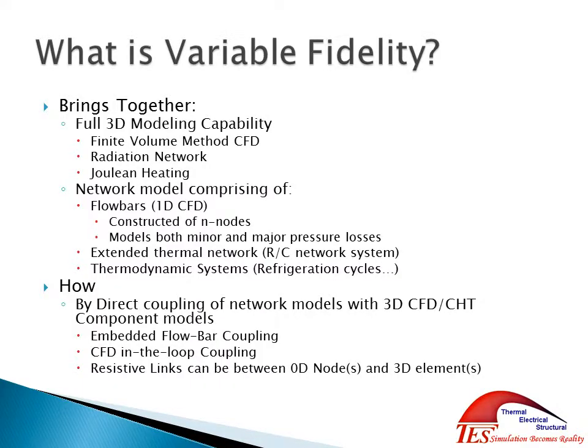First off, what do we mean by variable fidelity? Variable fidelity is bringing together both 3D modeling capabilities, such as CFD modeling with a full radiation network and any kind of Joule heating, and coupling that in with network modeling, where you can model 1D flow bars, looking at minor and major pressure losses through those systems, and also extended thermal network models using a resistance-capacitance network approach, as well as different thermodynamic systems.